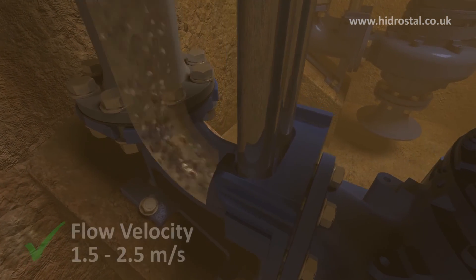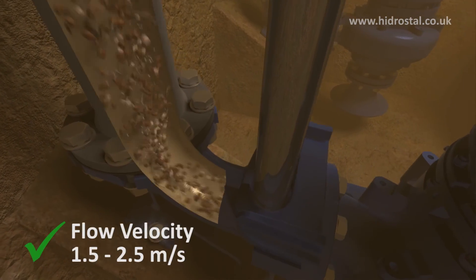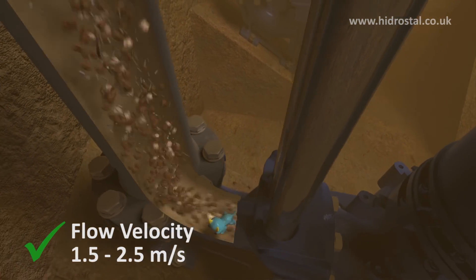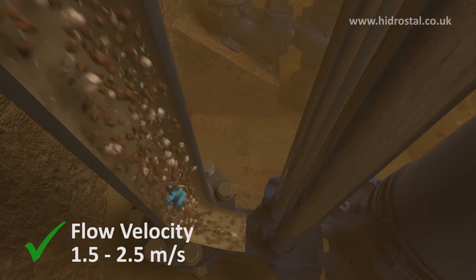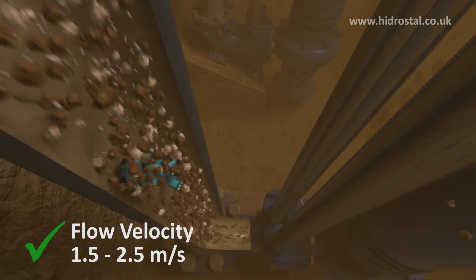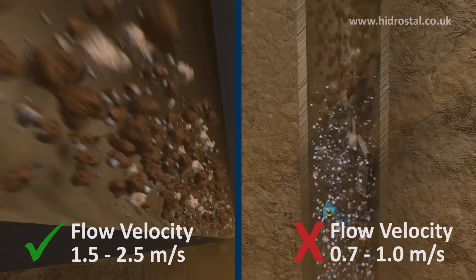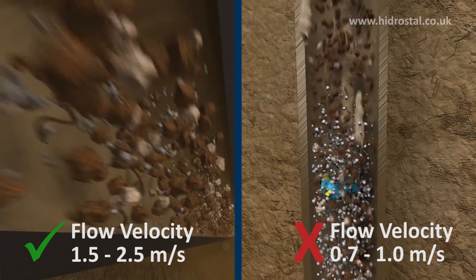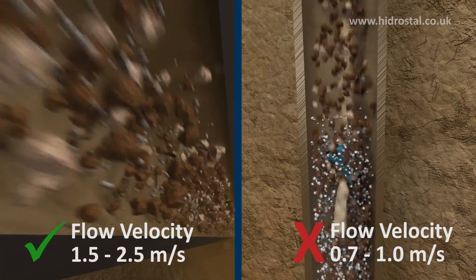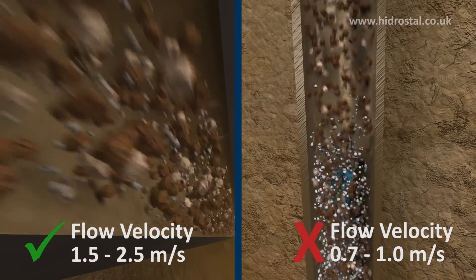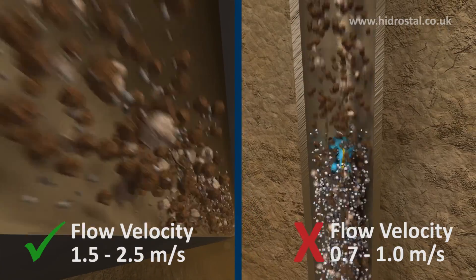The vertical discharge riser pipework should be sized to ensure a minimum flow velocity of 1.5 metres per second during the cleaning cycle, as levels approach the bottom water level stop point.